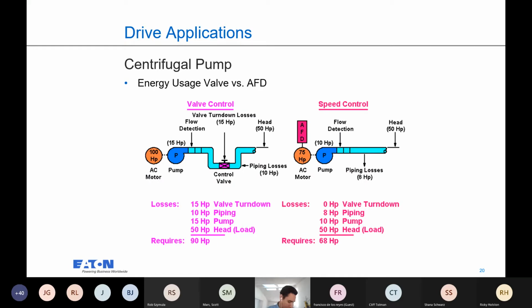And this is a good example just because a lot of times when we're designing pumps, VFDs, we do need some redundancy. So what I'm going to ask here is that we can use both methods. So let's think about this a little bit. So for this system, when we have a 100 horsepower motor, a pump, and we're using a valve to reduce the flow in the system, we're actually adding some head here. So we're adding head from the higher horsepower motor, we're adding head from the additional piping, the valve turn down. It requires a 90 horsepower to overcome that system flow.